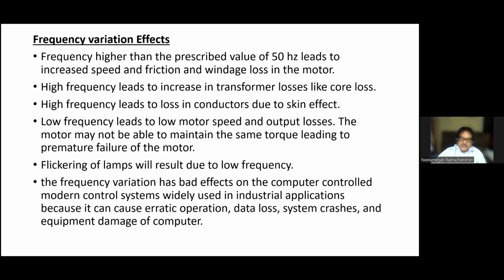So, frequency variation effects. High frequency leads to increased speed, friction and windage loss in the motor. High frequency leads to increased transformer losses; core loss will be more. There is also high frequency loss in conductors due to skin effect. Low frequency leads to low motor speed and output losses. The motor may try to maintain the same torque, leading to premature failure of the motor. There is also flickering of lamps. Variation has bad effects on computer control, which we have experienced: data loss, system crash, everything will happen with this frequency variation.